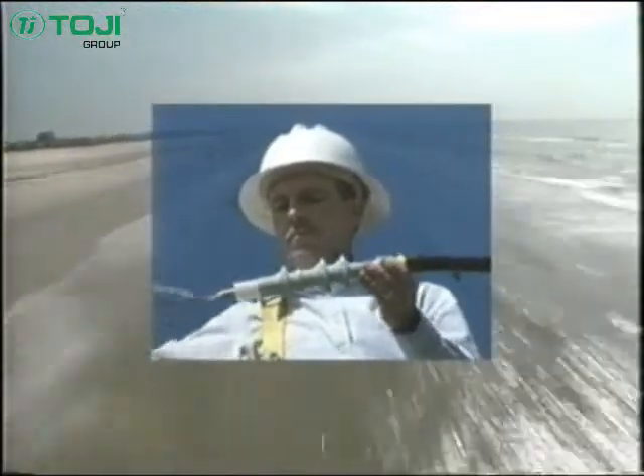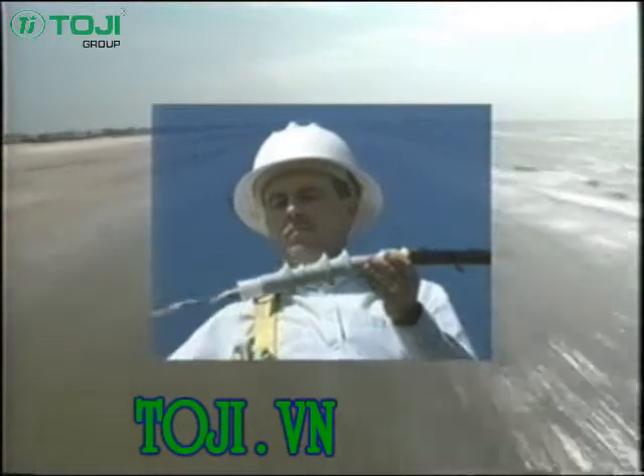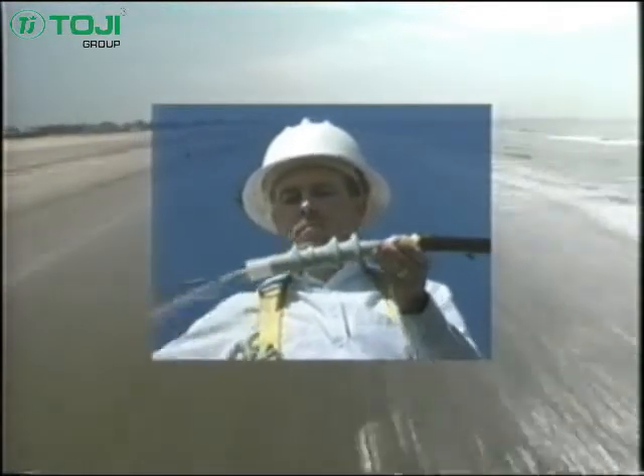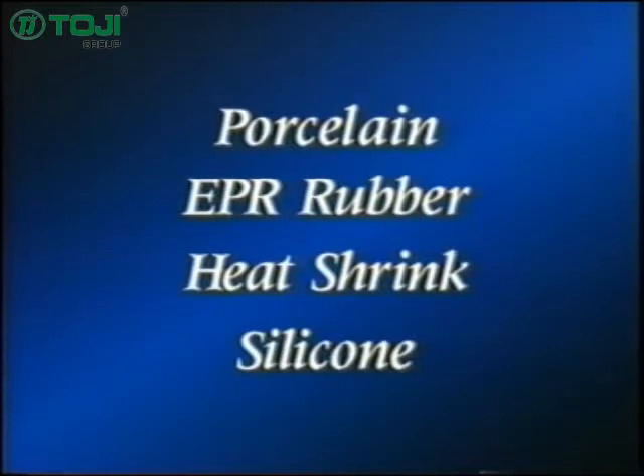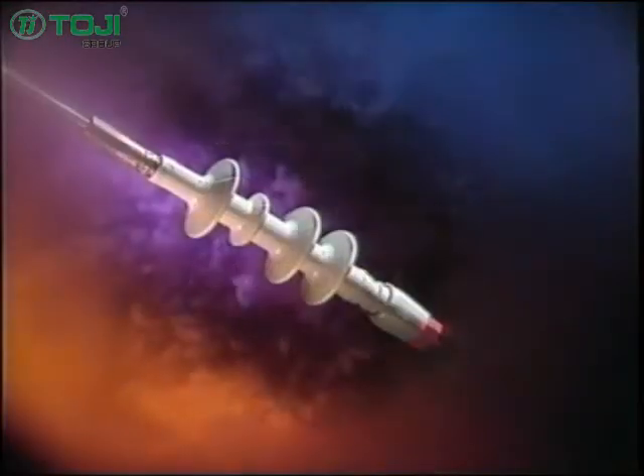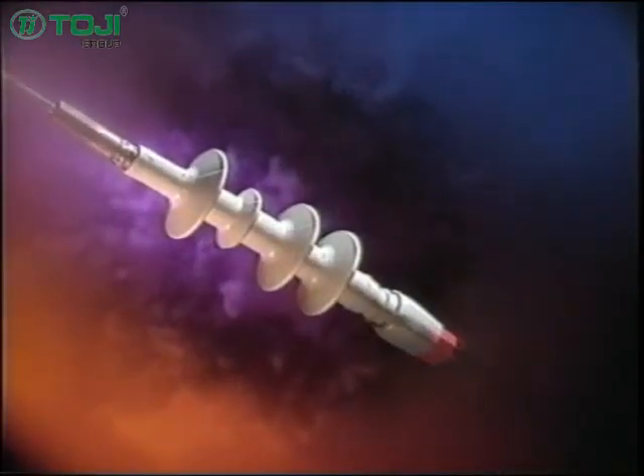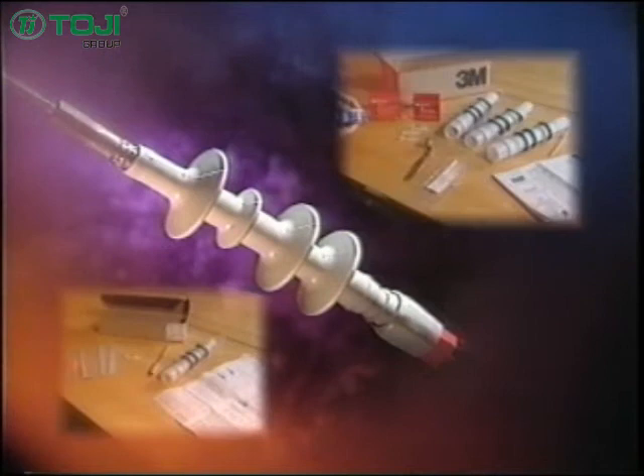Since we cannot control the environment, we have chosen materials for our termination insulators that can do the best job of resisting damage from tracking and environmental stress. There are four materials used for electrical terminations: porcelain, EPR rubber, polyolefin heat shrink, and silicone. We can show that our Cold Shrink silicone rubber Quick Term 2 kits are by far the best termination products available. First, silicone rubber handles moisture the best of any of the four materials listed.